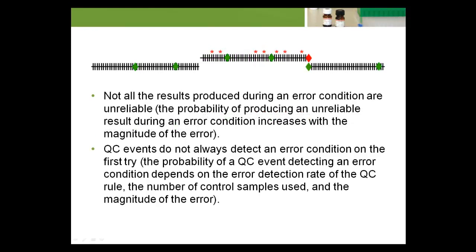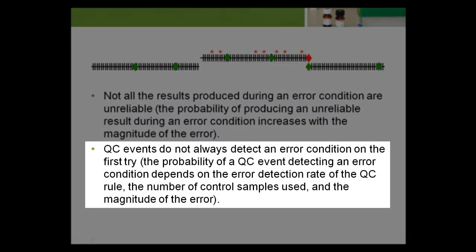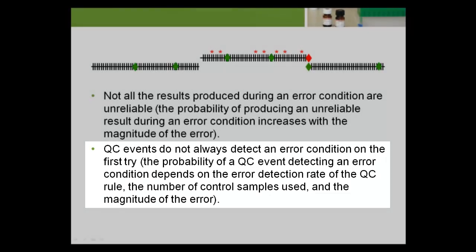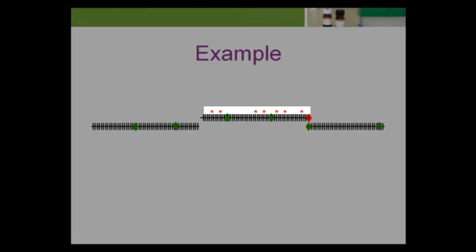Notice some of the important relationships between QC events, the number of patients tested between QC events, and the number of unreliable patient results. Not all the results produced during an error condition are unreliable. The probability of producing an unreliable result during an error condition increases with the magnitude of the error. QC events do not always detect an error condition on the first try. The probability of a QC event detecting an error condition depends on the error detection rate of the QC rule, the number of control samples used, and the magnitude of the error. If the error condition in the example was smaller, we would expect proportionally fewer of the results tested during the undetected error condition to be unreliable, but more QC events needed to detect it.